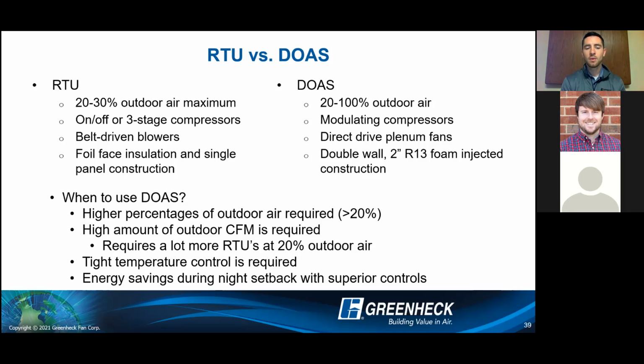the minimum required. When that's the case, if RTUs are only designed for 20% outside air, now you have to start adding 2, 3, 4, 5 rooftop units just to be able to handle the outdoor CFM that you want to use, versus 1 or 2 DOAS units that could handle that CFM in a much smaller housing, which obviously reduces installation time. So as you're thinking about bringing in more fresh air during these tough times and during the pandemics and epidemics and things like that, think about looking at DOAS, even if it's only around that 20 to 30% outdoor air, because you're going to get smaller footprints and you're going to get fewer units.